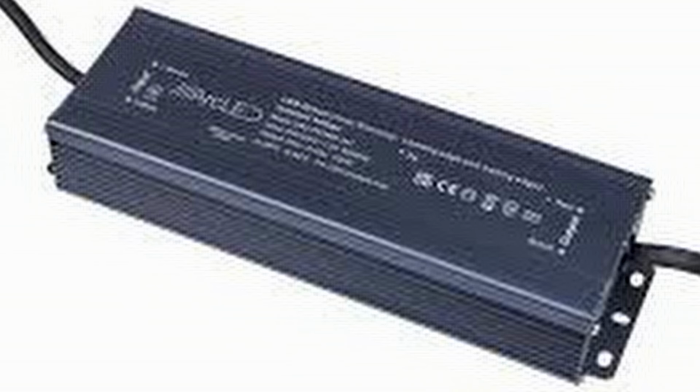Why does it matter? Number one, LEDs are electronic systems. They're not just bulbs. You've got an LED driver, then you've got the bulbs. The driver is like a little black box. If you get an LED light, you see it's a little black box. It converts the AC power into DC, because LEDs actually operate on DC, which is what the light operates on. Those drivers dissipate a lot of heat, so there has to be enough space within the ceiling for ventilation, for the air to move to dissipate the heat, otherwise it's a fire risk.